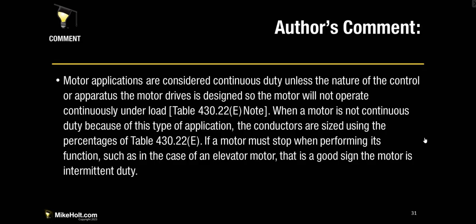Motor applications are considered continuous duty unless the nature of the control or apparatus the motor drives is designed so the motor will not operate continuously under load. When a motor is not continuous duty, because of this type of application, the conductors are sized using the percentages of table 430.22(E), running down through my code book here. Table 430.22(E), duty cycle service.